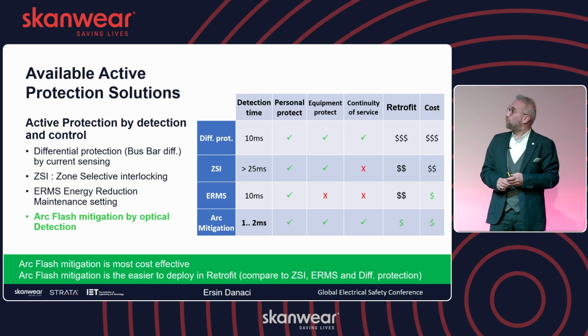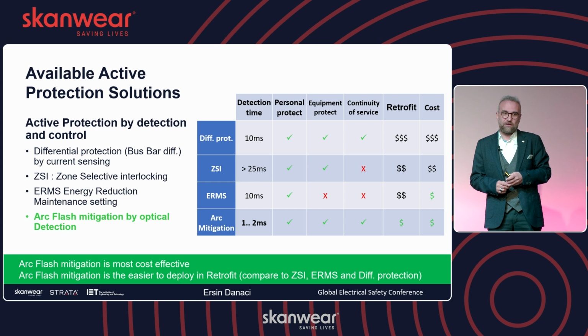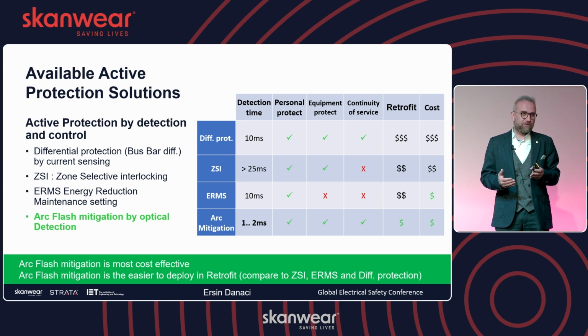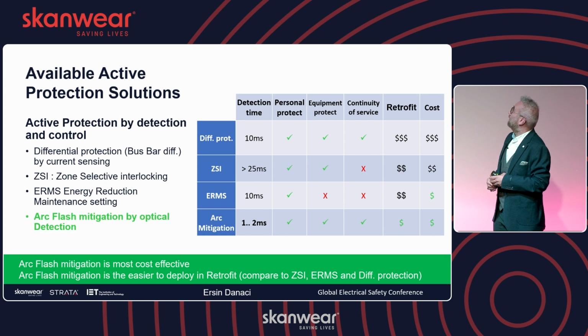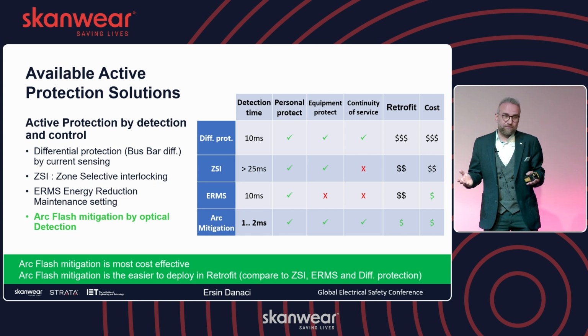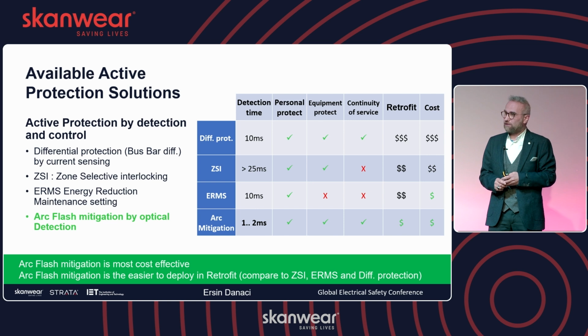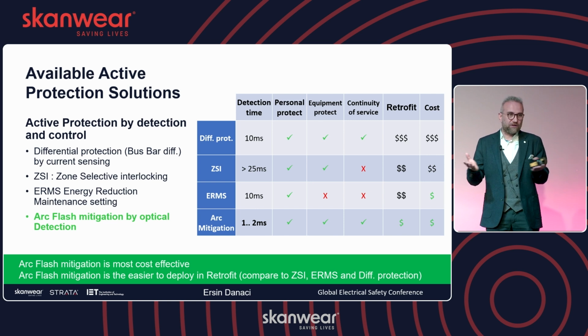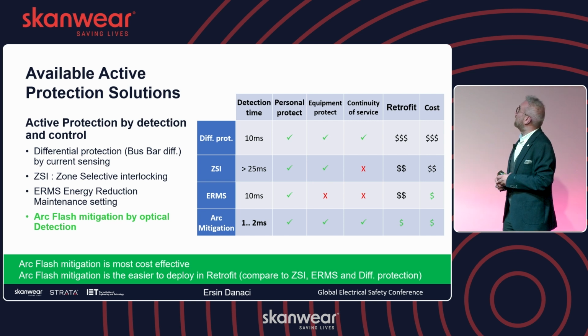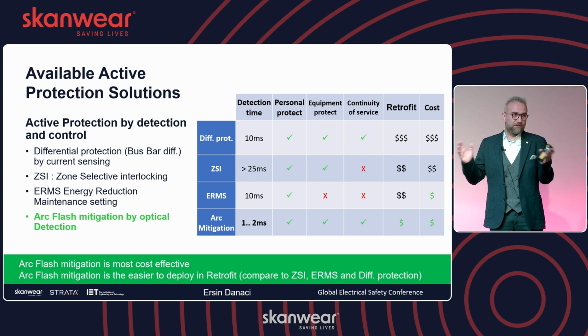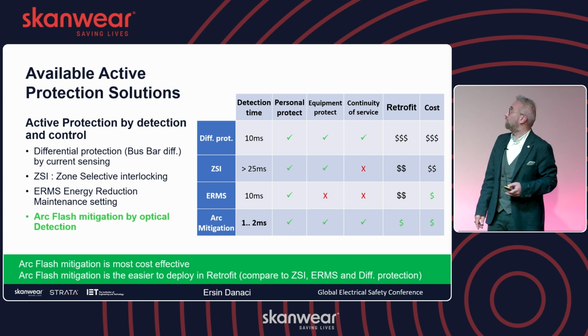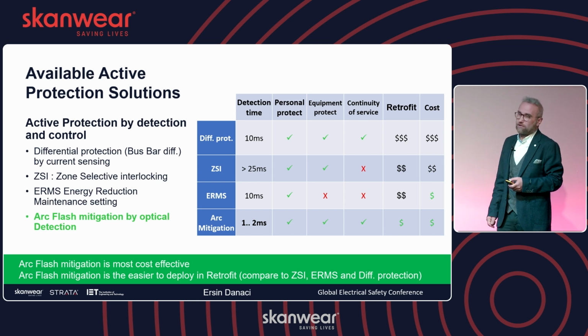So for example, for the differential protection, we can also utilize a busbar protection. It's another mitigation. But for the busbar protection, we may need to use specific CTs. That means it will be a bit more expensive. And also, if you consider the low impedance protection, then we may not be able to protect the cable compartment. So there are some disadvantages to the different mitigations, but that's the reason we are advising the arc flash technologies, which are specifically designed for this type of application, for the arc flash issues.